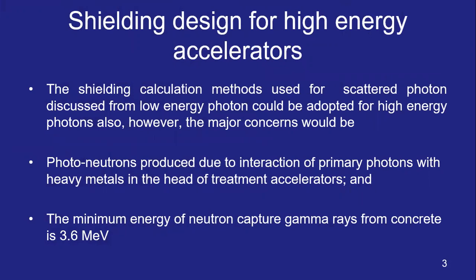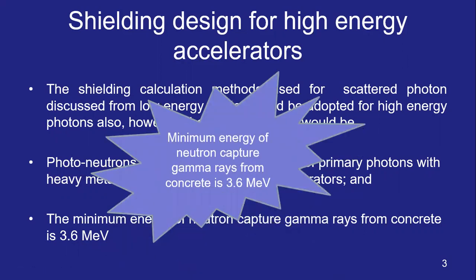The shielding calculation methods used for scattered photons of low energy beams can be adapted for high energy photons. However, there are two additional things to consider. One is photoneutrons produced by interaction of the primary photon with heavy metals in the treatment head of the linear accelerator. Second, these photoneutrons, when passing through concrete barriers, produce neutron capture gamma rays. The minimum energy of these neutron capture gamma rays is 3.6 MeV. The barrier must account for both photoneutrons and neutron capture gamma rays.